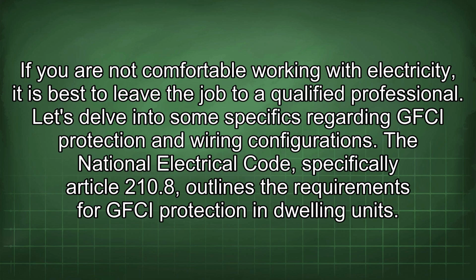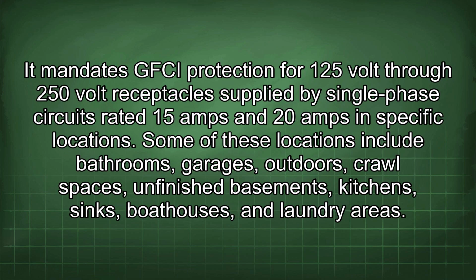Let's delve into some specifics regarding GFCI protection and wiring configurations. The National Electrical Code, specifically Article 210.8, outlines the requirements for GFCI protection in dwelling units. It mandates GFCI protection for 125V through 250V receptacles supplied by single-phase circuits rated 15A and 20A in specific locations. Some of these locations include bathrooms, garages, outdoors, crawl spaces, unfinished basements, kitchens, sinks, boathouses, and laundry areas.